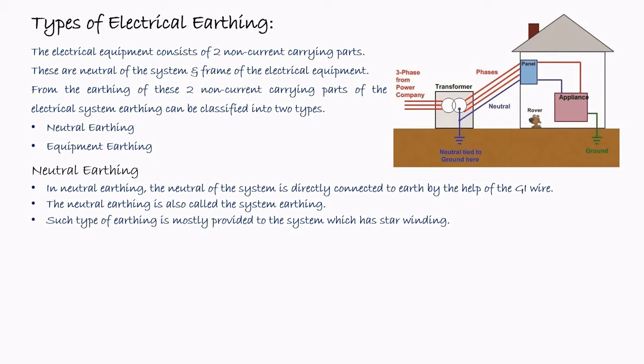Normally the transformers and the power systems are used as a three-phase system. So the distribution transformer secondary side is always star connected. Therefore, the star terminal should be earth connected so that if there is any fault or any unbalanced condition, then the extra current will flow to the earth through this neutral star terminal. For example, the neutral earthing is provided to the generator, transformer, and motors that are connected to three-phase supply as well as for the single-phase supply also.